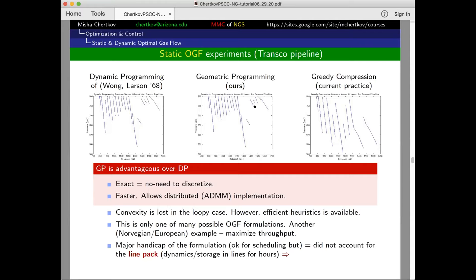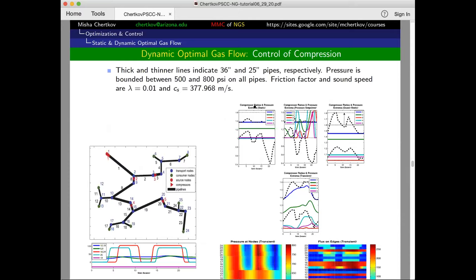How about dynamics and line pack? In this approach — using the lumped-element discretization — you can certainly extend it to this case. It's basically an optimal control type of problem. Your degree of freedom is compression. You may assume you know the consumption injections, and then you are looking for the compression schedule. Your solution gives you pressure as a function of time and flux as a function of time.